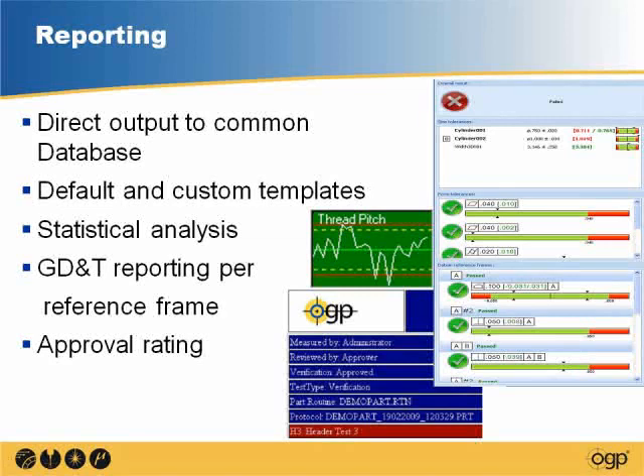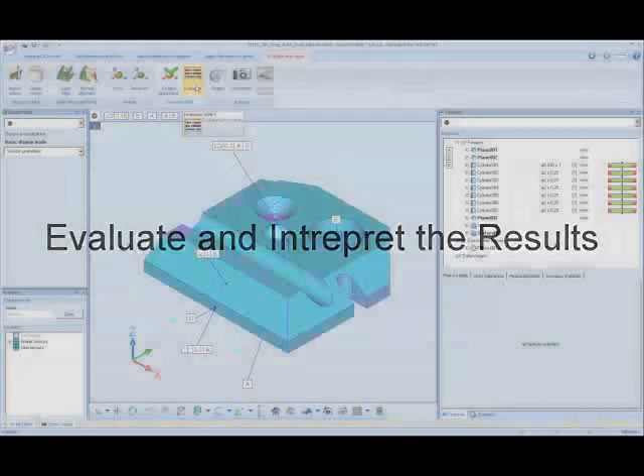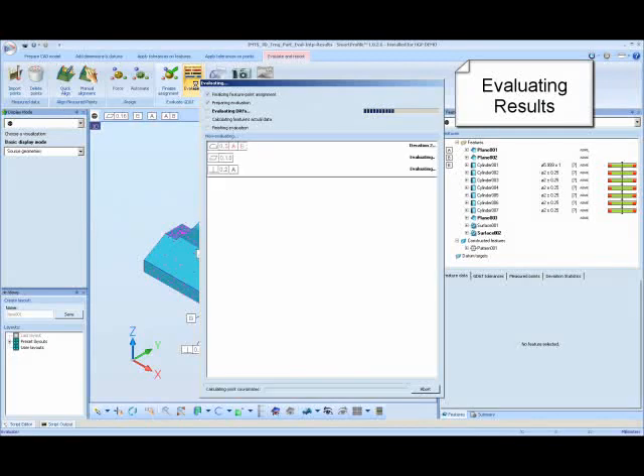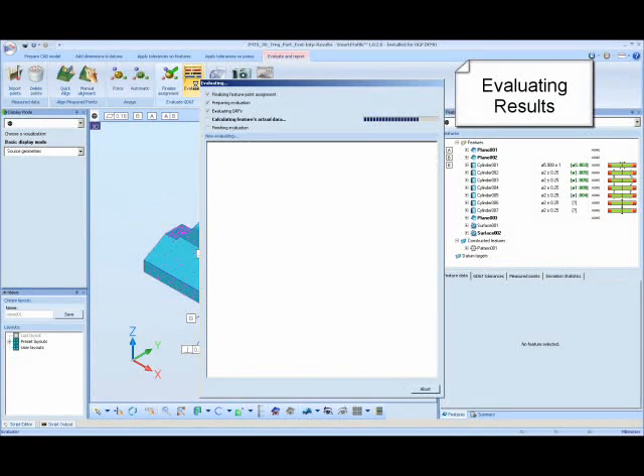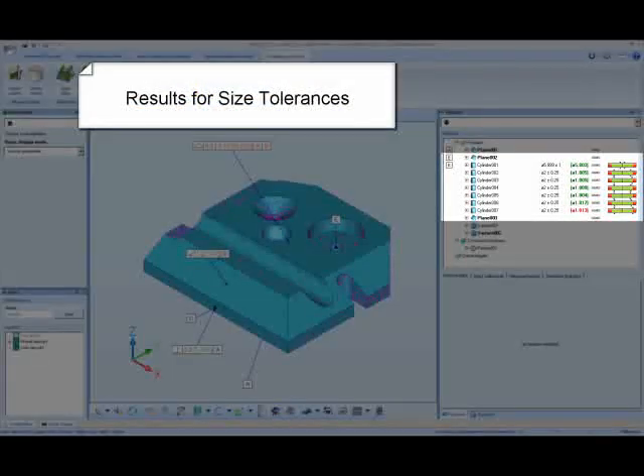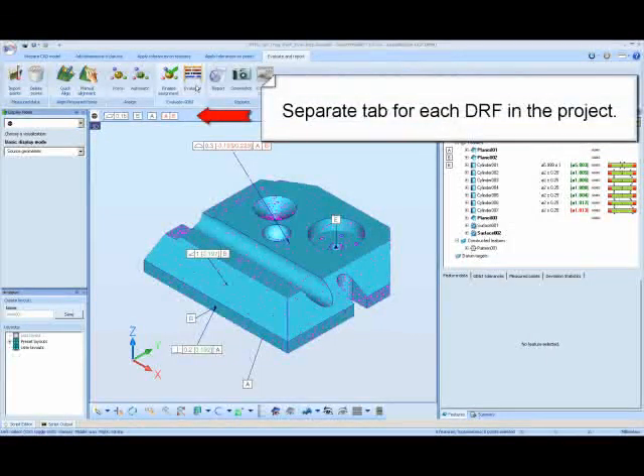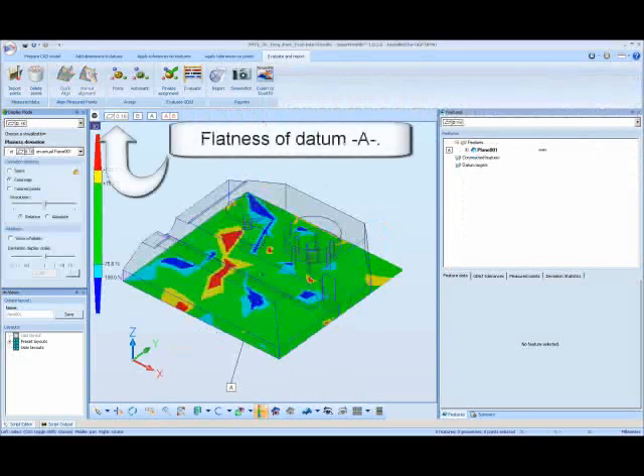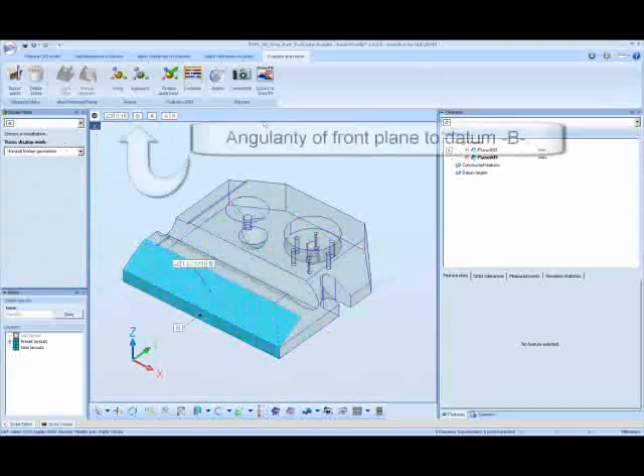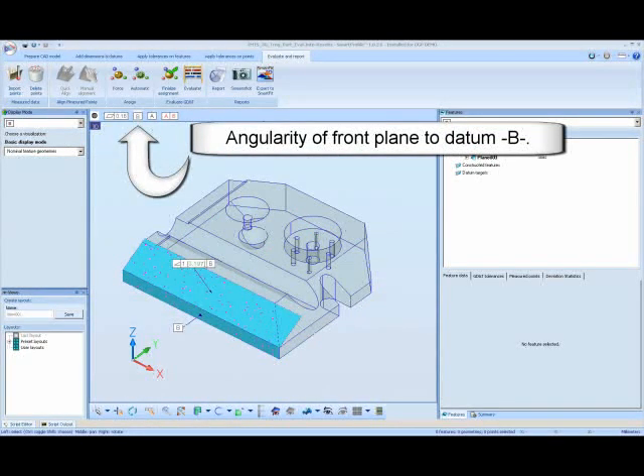So let's look at one example of a pretty nice report. This one is more related to GD&T. It's taking a CAD model, fitting the data onto it, and evaluating these different kinds of criteria that are necessary on this particular part. So there are different datum reference frames, different profile tolerances, different size tolerances. And depending on the kind of call-out that it is, sometimes it needs to move that data around differently to determine those things. So you get the angularity, the flatness call-outs, the profile tolerances, perpendicularity of B relative to A. This is a free-form surface profile relative to A and B. You get the color map of it. And then at the end you get an indication of failed or passed overall, and then within the different datum reference frames.